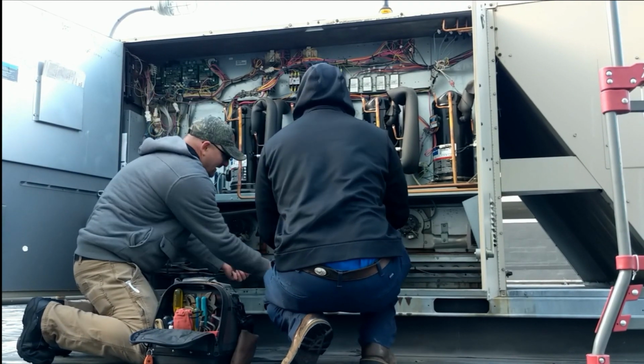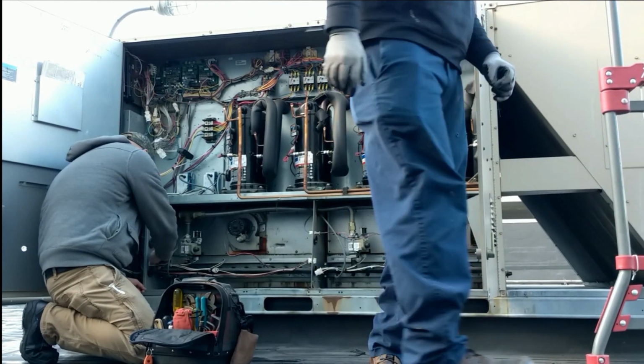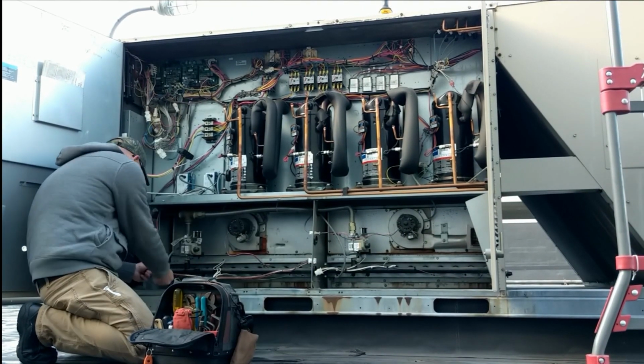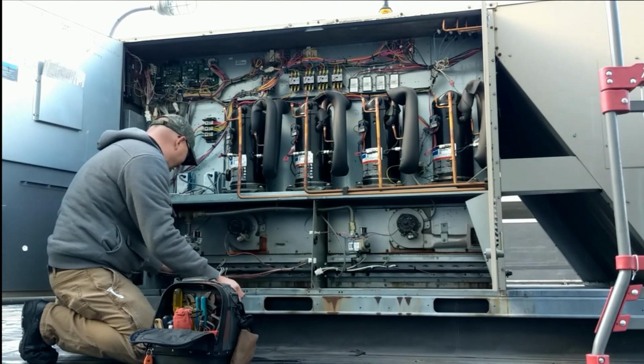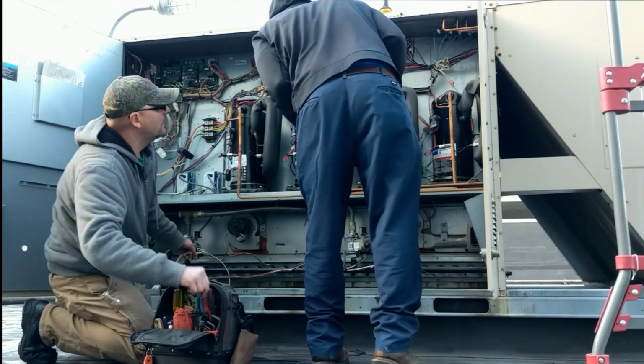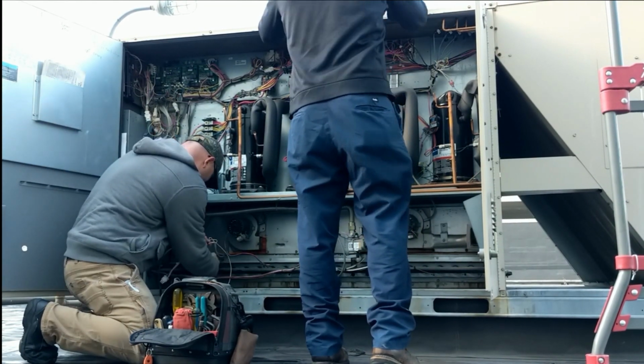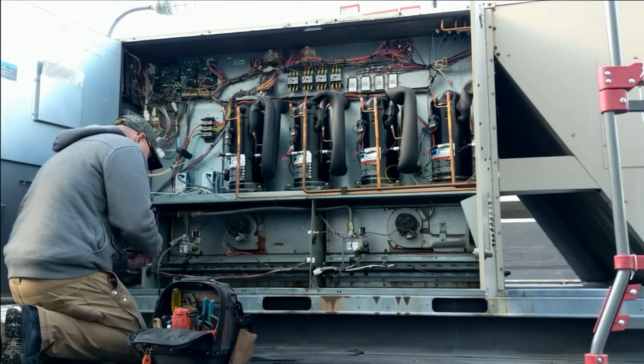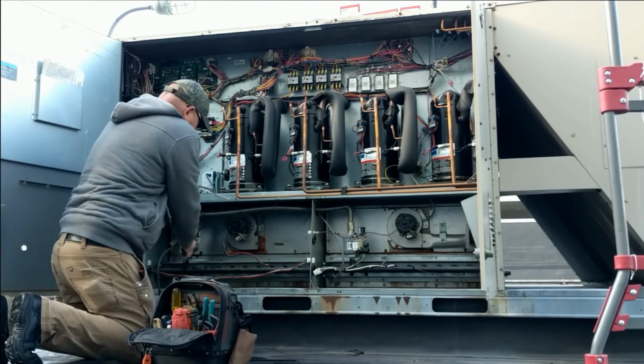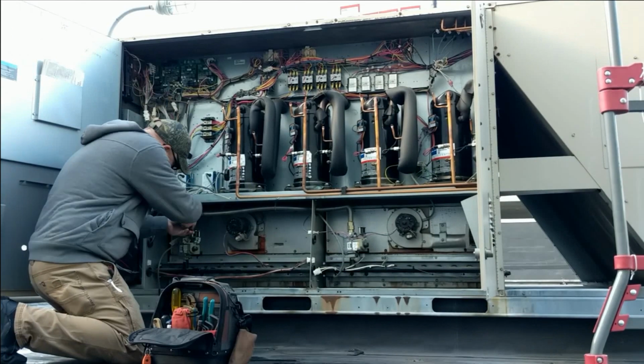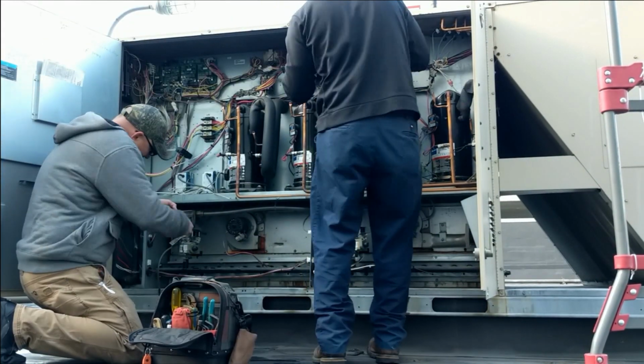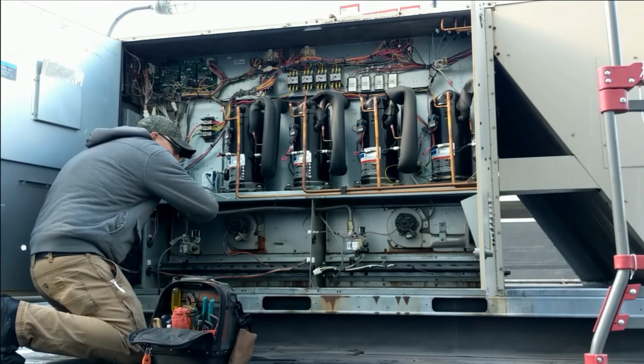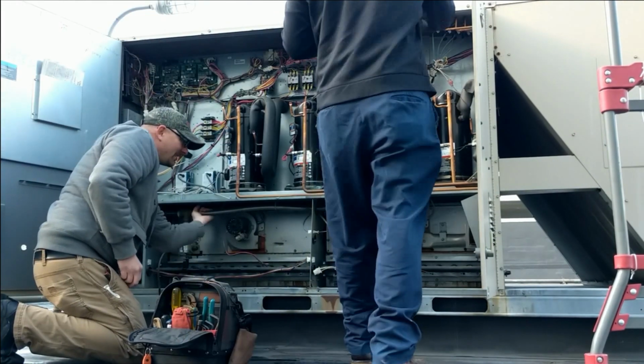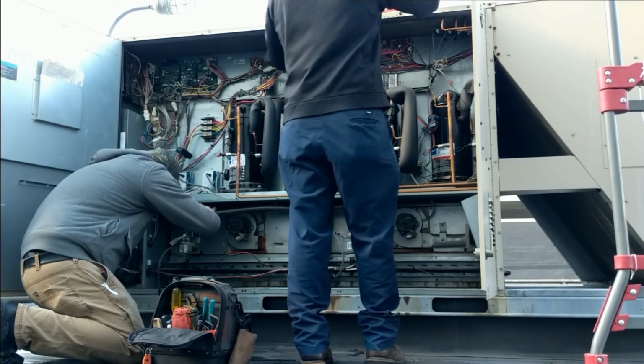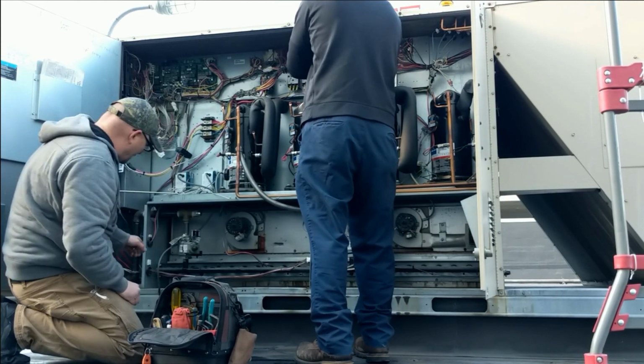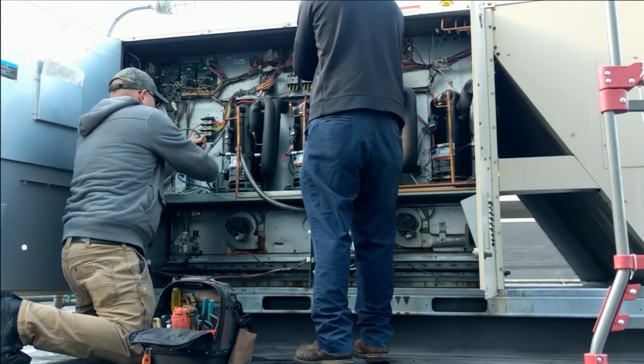Alright, basically, after we shut the gas and the electric off to the unit, we just start pulling all the wiring out, wiring harness, gas manifold, the flexible gas line between the two gas valves. We're going to take that out, and we're going to strip everything off of the face of the heat exchanger and get ready to pull all the screws that secure it out and just prep it to pull the heat exchanger out.